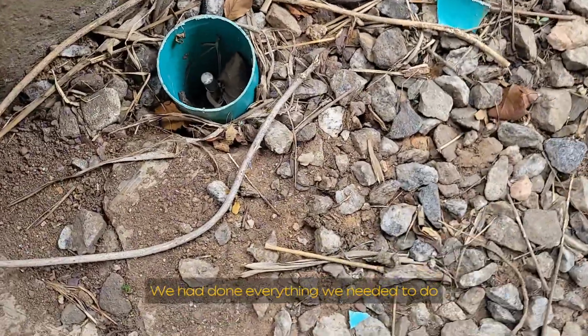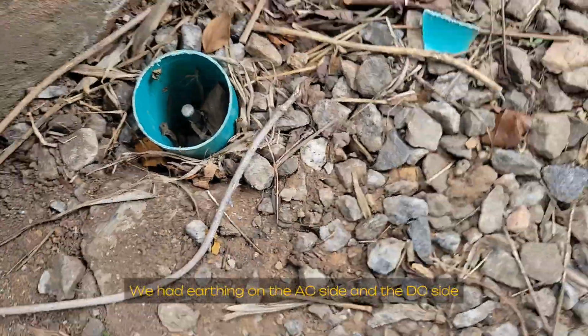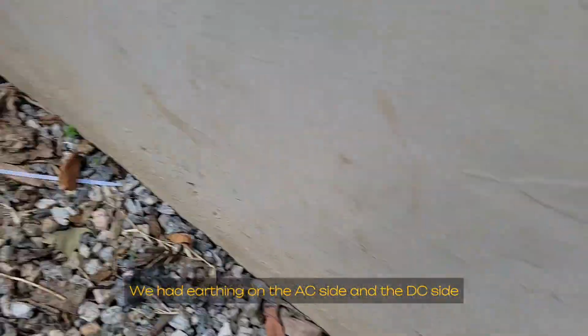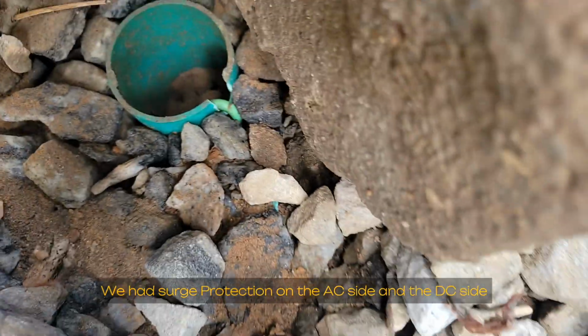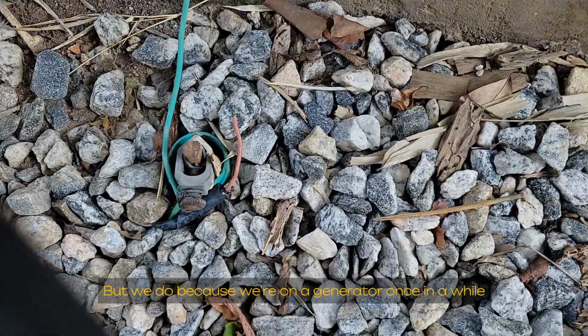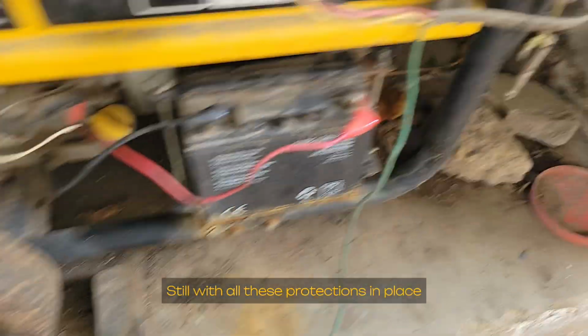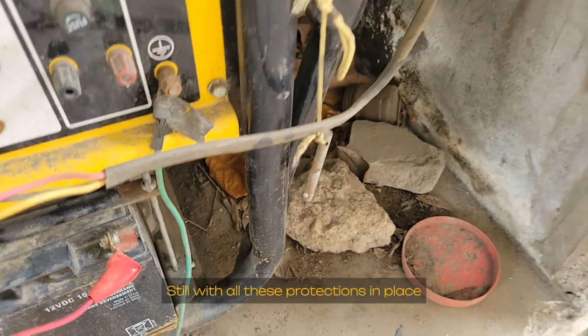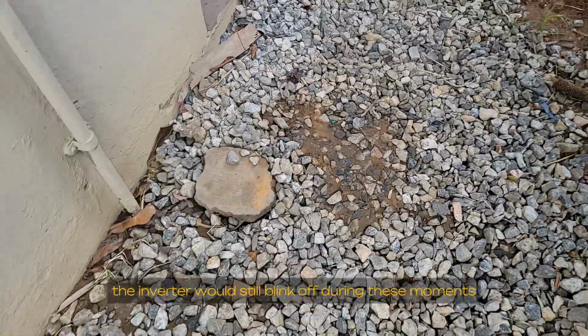We had done everything we needed to do. We had earthing on the AC side and the DC side. We had surge protection on the AC side and the DC side. As you know, I'm off-grid, so there's no need for surge protection on the input side, but we do because we run a generator once in a while. Still, with all these protections in place, the inverter would still blink off during these moments.